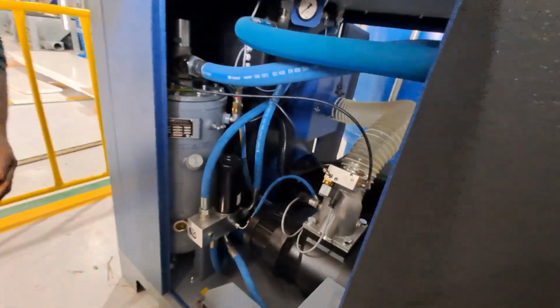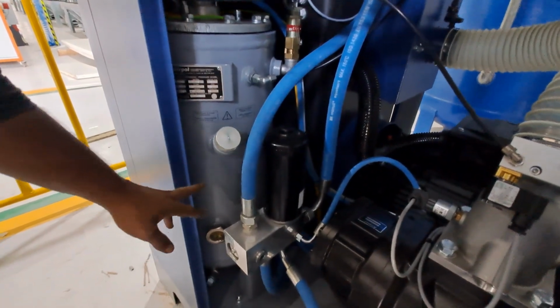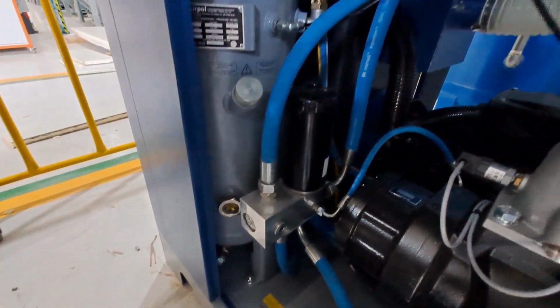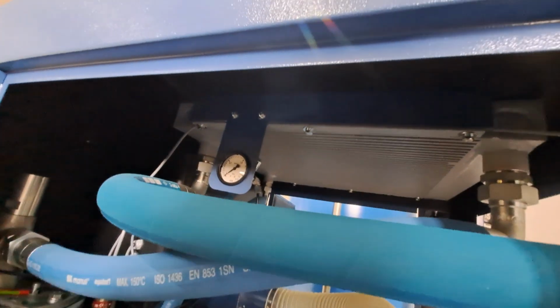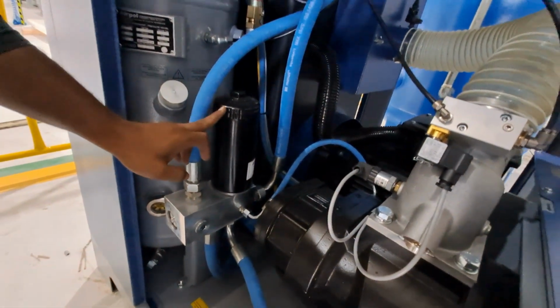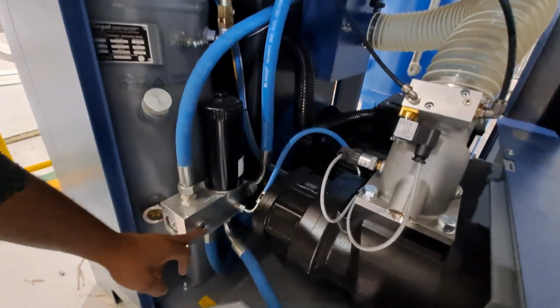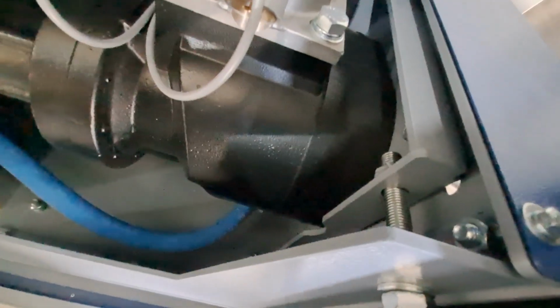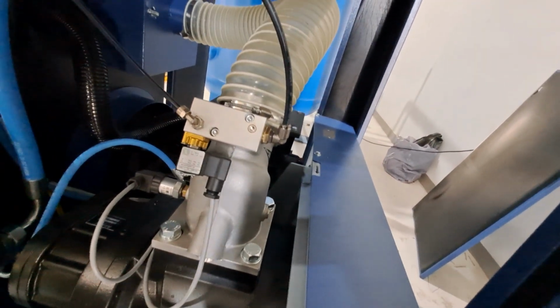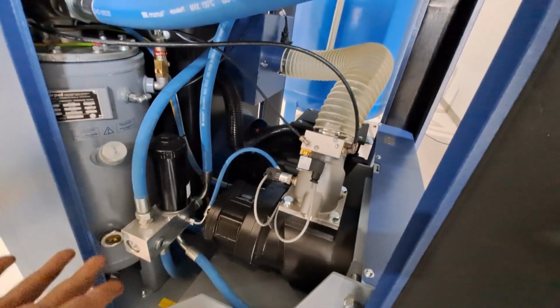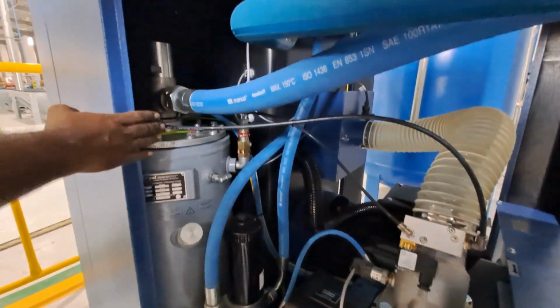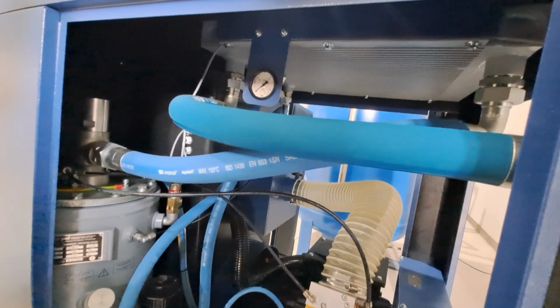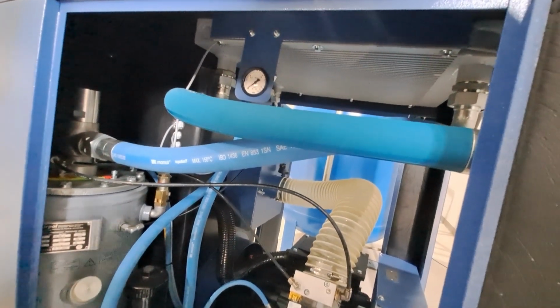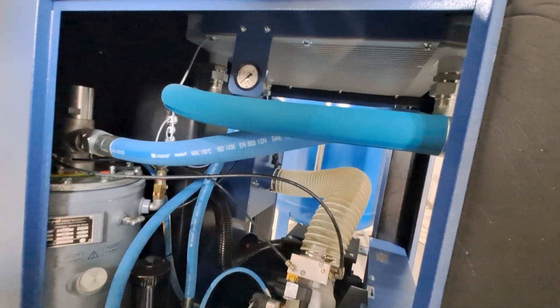And coming to the oil which is separated in the oil tank, this oil will go to the cooler, and in the cooler the oil gets cooled and comes back to the oil filter. In the oil filter the oil gets filtered and returns back to the air end. In the air end, air and oil again get mixed for the lubrication and cooling of the air end. Then the oil again travels to the oil tank. This cycle process will repeat, cooling the air and oil in the system.